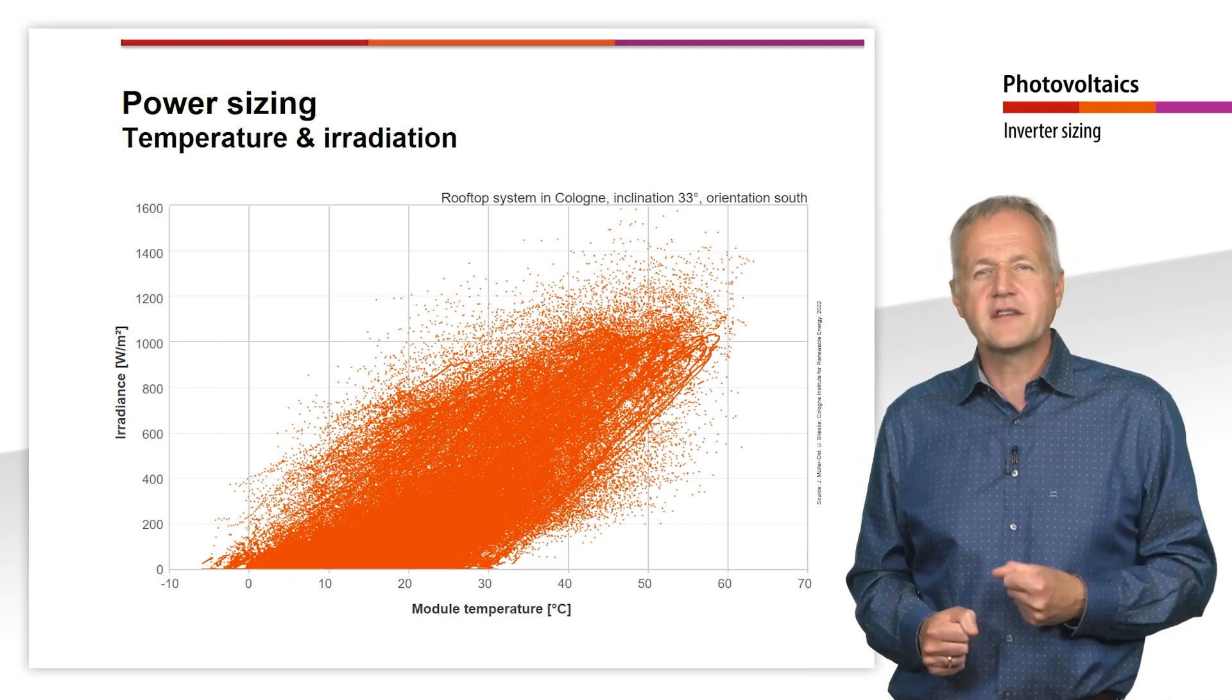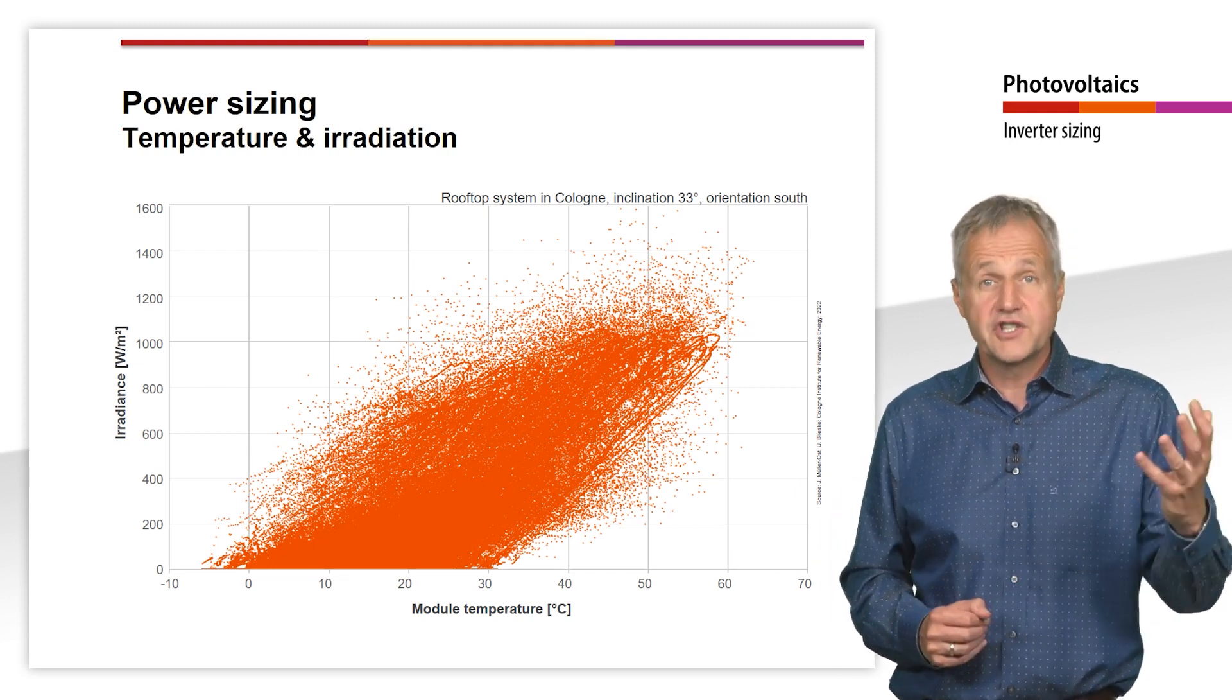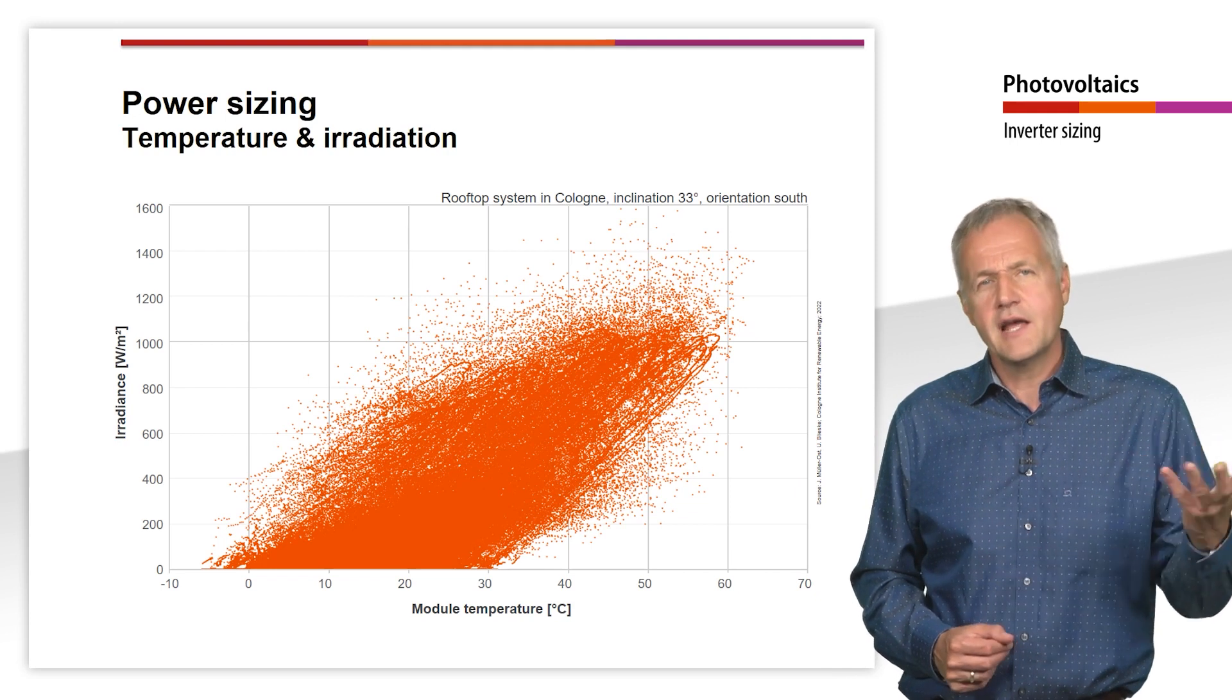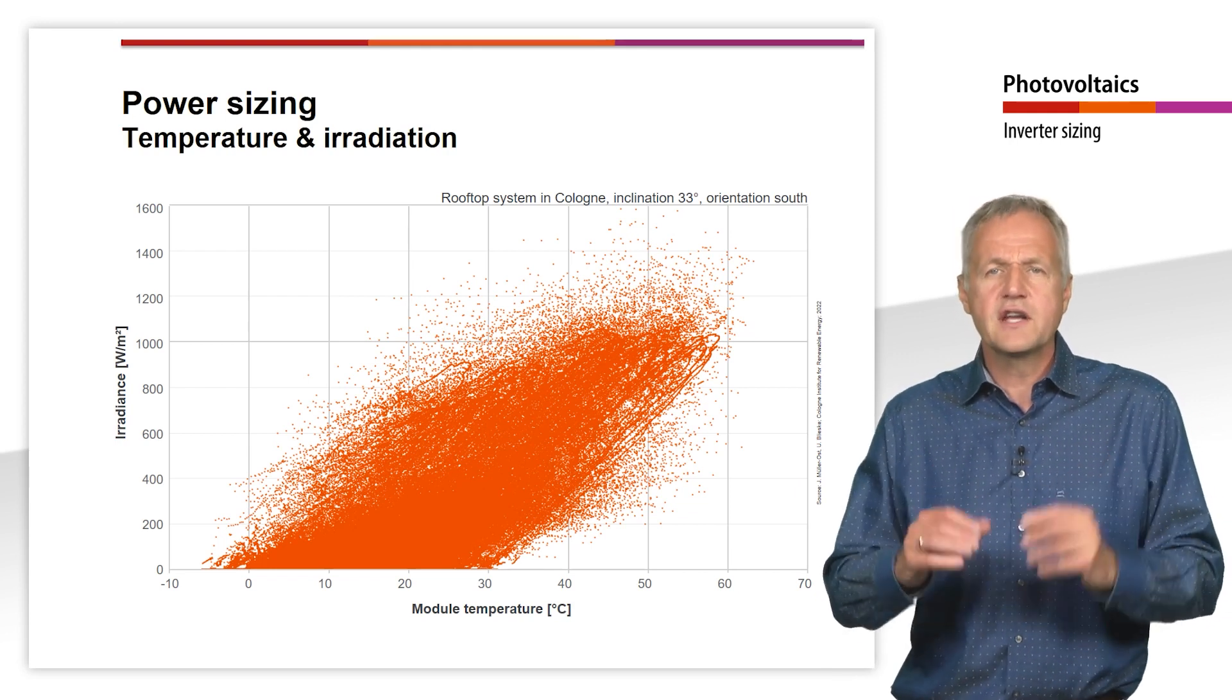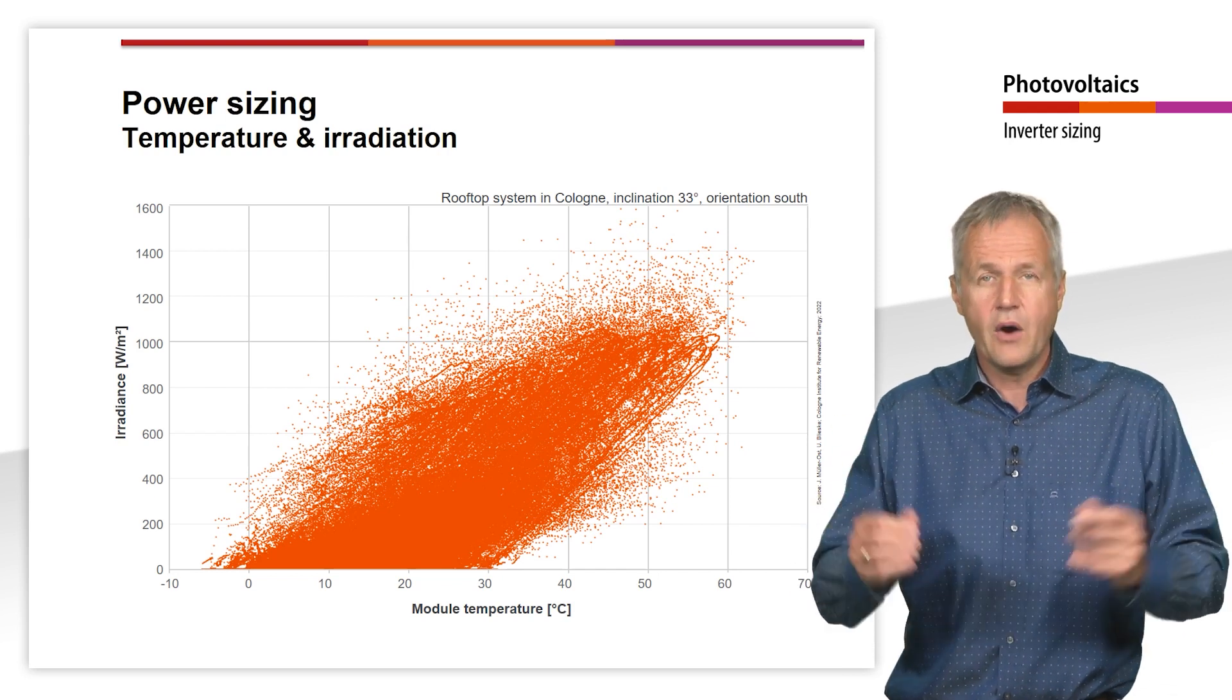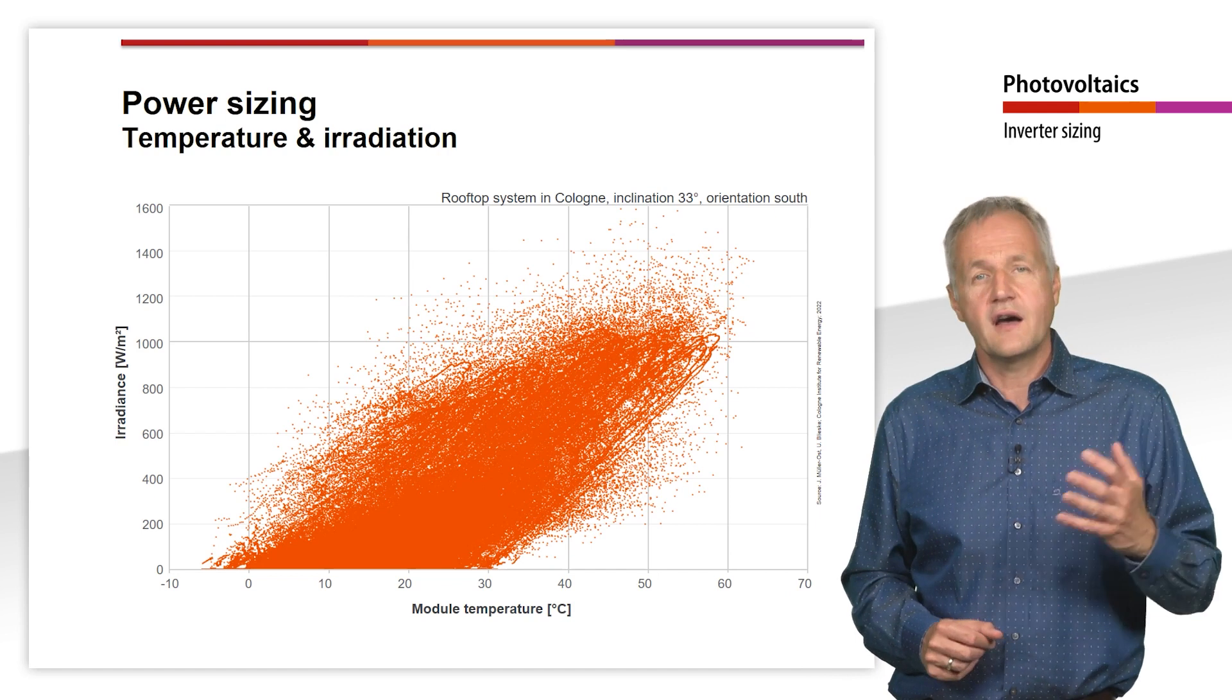However, in practice, it is common to size the inverter somewhat smaller than the solar generator. The reasons for this are mainly economic considerations. Since the cost of the inverter increases with its rated power, while the yield losses are very small if it is undersized.